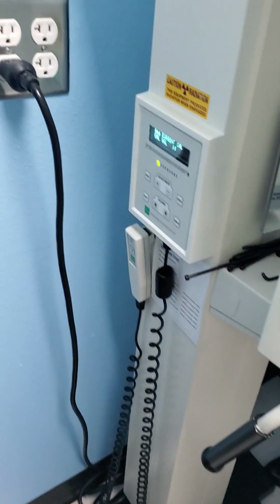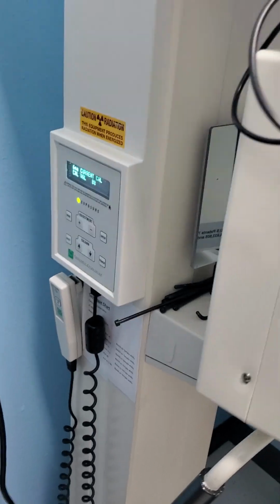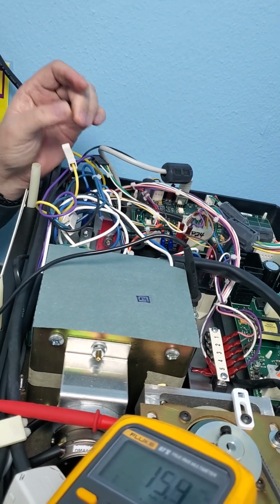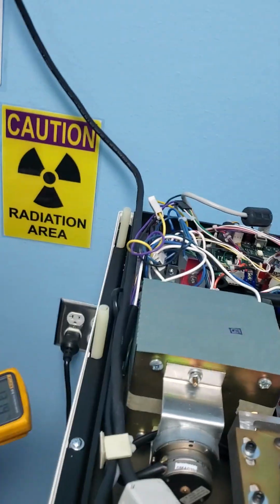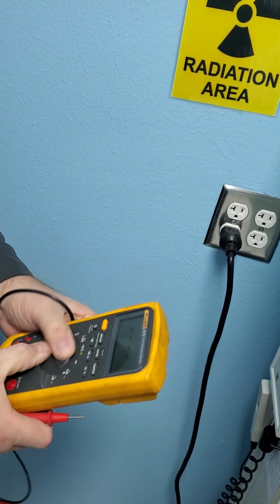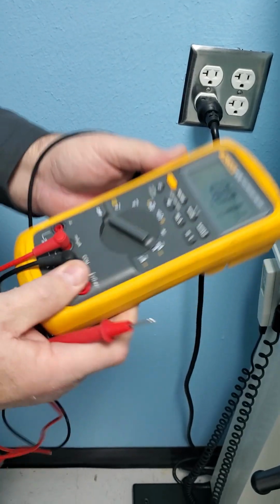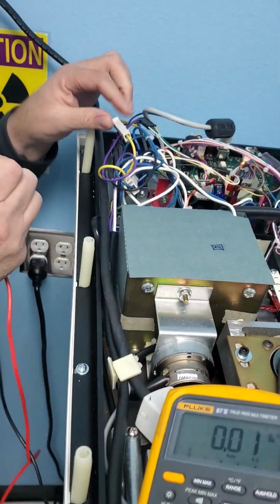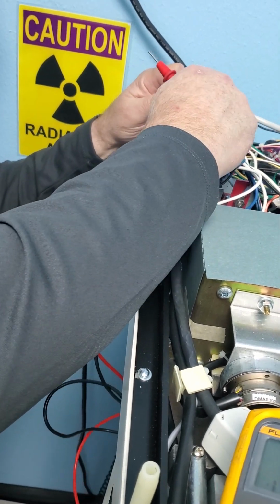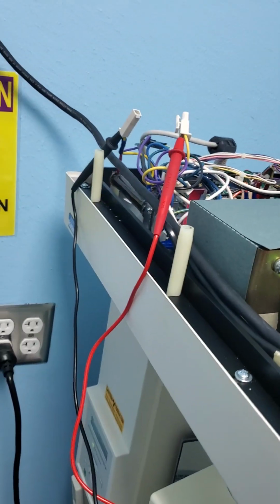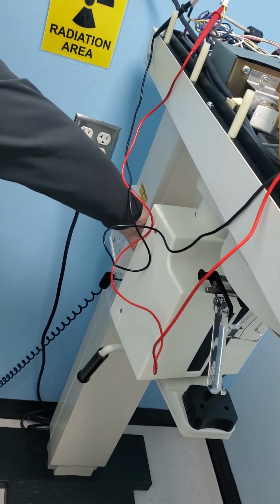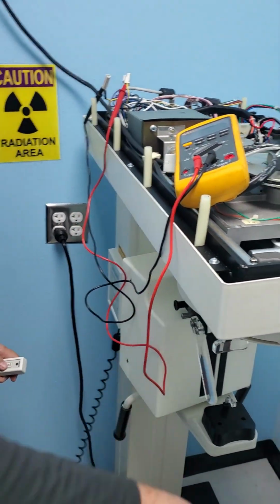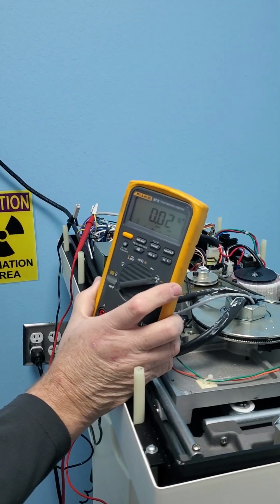Okay. The next one is MA current cal, and for that, this is where you read the MA. You have to get in series. You have to switch your meter to read MA, and you want DC MA. You put one probe in one end of the plug and one probe in the other, and then unplug it and separate them. What you've done is put the meter in series of that MA line. Then we're going to shoot. The beam's knife shape. It's very narrow, and it's coming to here, and there's a 1-inch thick plate right here. So all the radiation's between here and here. We'll shoot and see what MA we get.